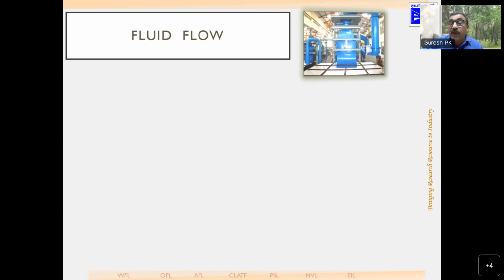And most important, you have to use a correct flow meter with a calibrated hierarchy to measure the flow. Fluid flow rate measurements are established. See, the fluid flow meters are affected by the fluid flow rate. That is, the performance of the fluid flow meter changes from flow rate to flow rate. Suppose you have a flow range from 1 to 100 meter cube per hour, and you use the same flow meter, let's say a 3-inch or 4-inch flow meter, at 1 meter cube per hour and at 100 meter cube per hour. It may not show the same accuracy at 1 meter cube per hour as it shows at 50 or 100 meter cube per hour. Therefore, the selection or proper sizing of the flow meter is very, very important, so that it can show the necessary accuracy in the operating fluid flow rate range.